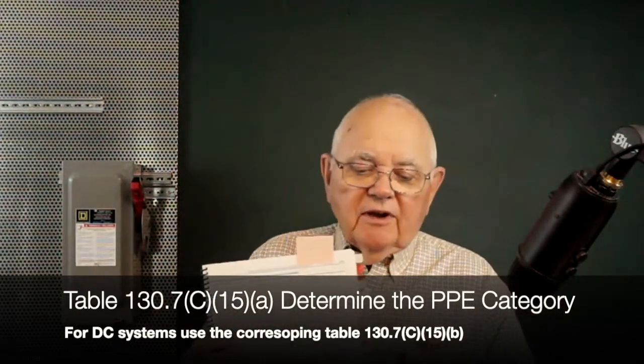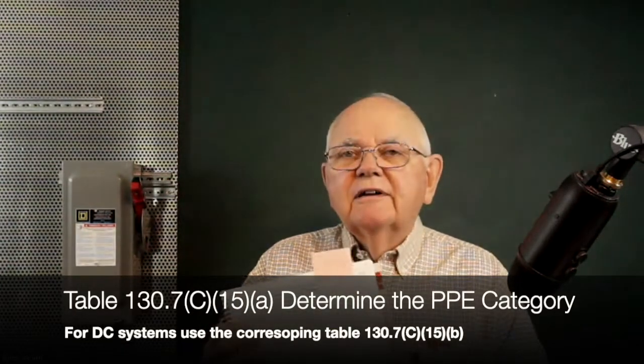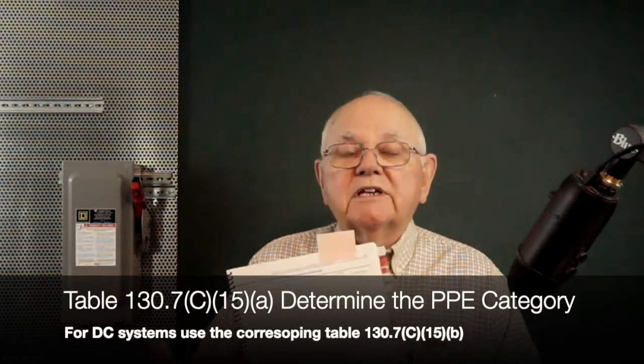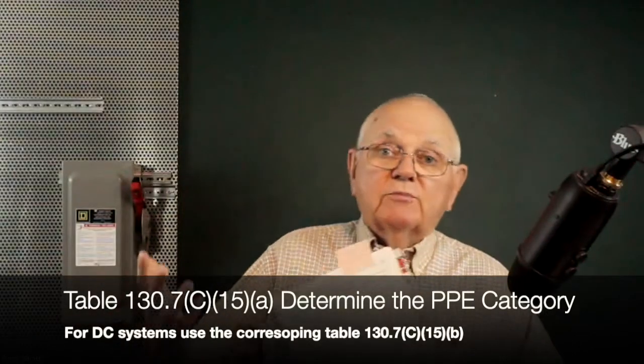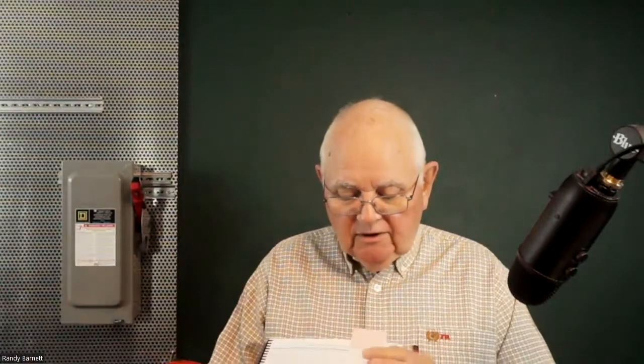Now, this particular table has three columns to it. The first column gives me the type of equipment it is: panel board, switches, circuit breakers, motor control centers, medium voltage equipment, whatever it is. The second column over tells me the PPE category. I don't know much about the PPE category yet, but this will tell me the PPE category. And then the last column tells me the arc flash boundary. That's going to be where the incident energy drops to 1.2 calories per centimeter square, which would be the onset of a second-degree burn then.